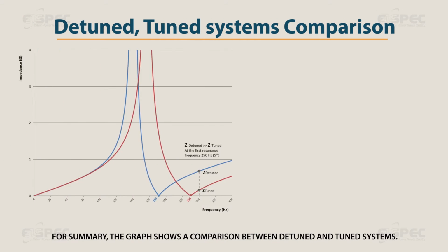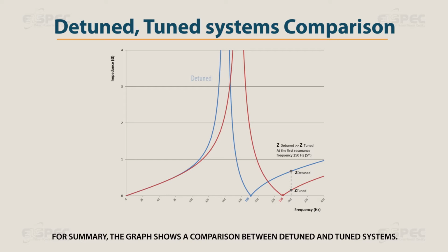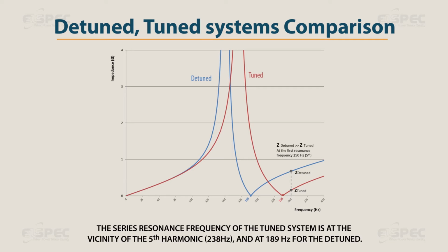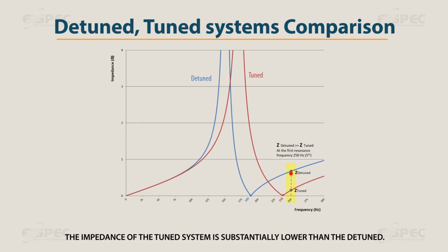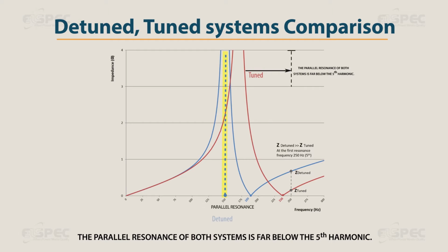In summary, the graph shows a comparison between detuned and tuned systems. The series resonance frequency of the tuned system is in the vicinity of the 5th harmonic, at 238 Hz, and at 189 Hz for the detuned. The impedance of the tuned system is substantially lower than the detuned. The parallel resonance of both systems is far below the 5th harmonic.